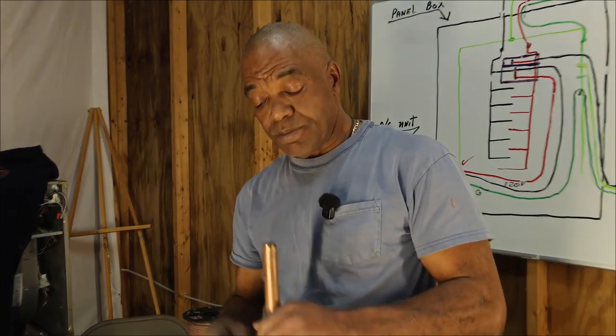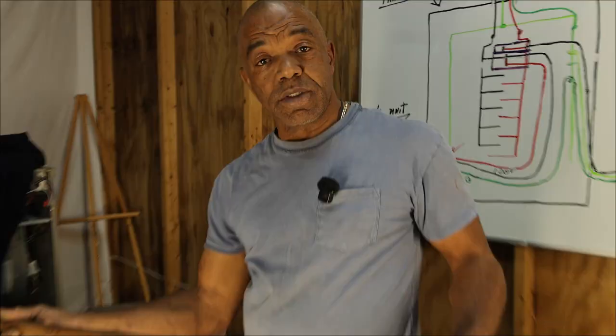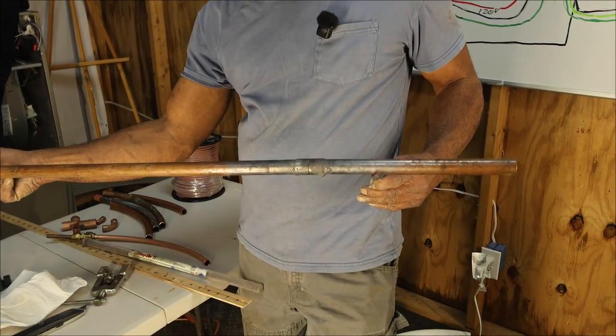That has the potential of damaging your system. It can clog up your orifice. It can, in large volumes, hurt the compressor. The way you prevent that is while you're brazing, you always run a minute amount of nitrogen through the copper while you're brazing. I'm going to teach you that also, but because this is open copper, it's not connected to anything, there's no way for me to hook my nitrogen up to it right now.